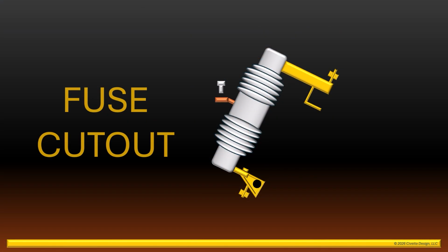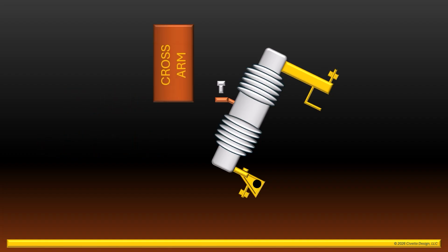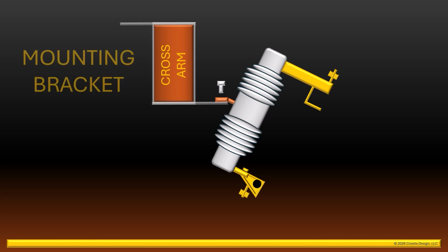This is called the fuse cutout. It's comprised of a corrosion-resistant steel frame along with a ceramic or polymer insulator. The insulator electrically isolates a steel mounting tab from the frame. The mounting tab allows the cutout to be attached to a wood or fiberglass crossarm using a steel rectangular mounting bracket that's attached to the crossarm.